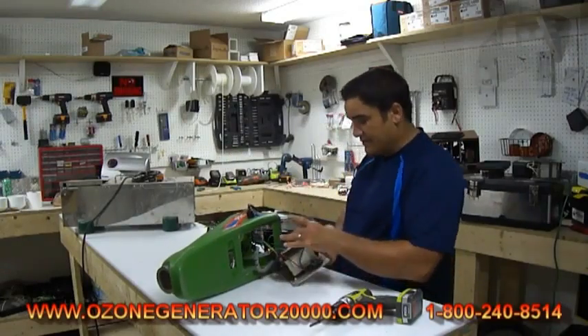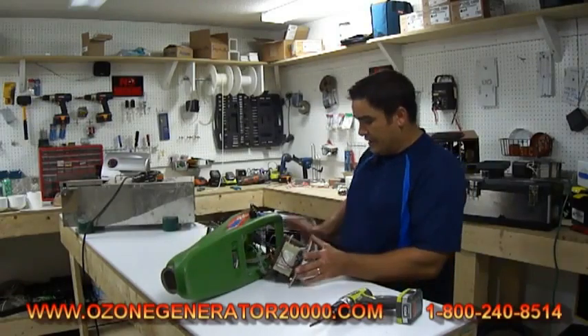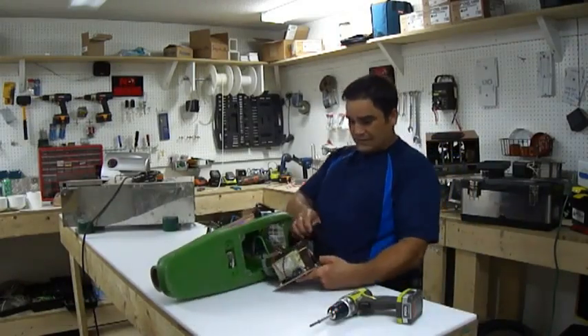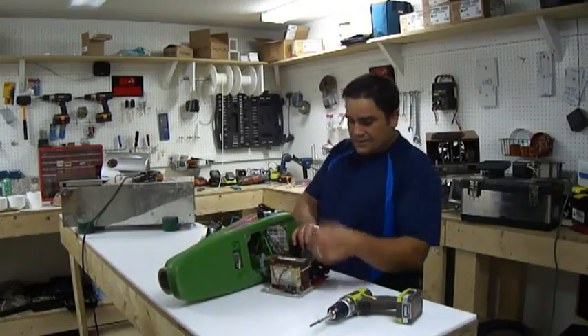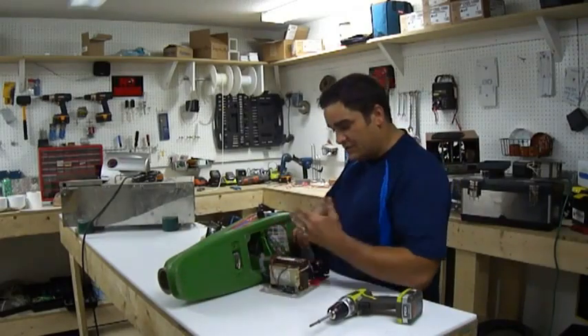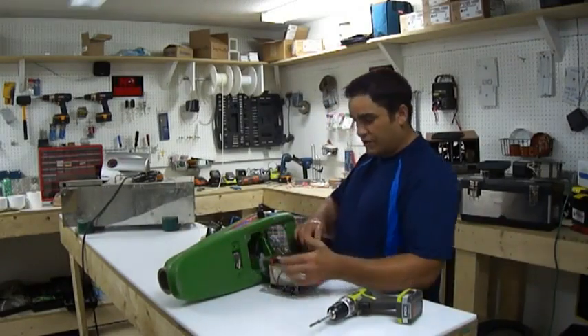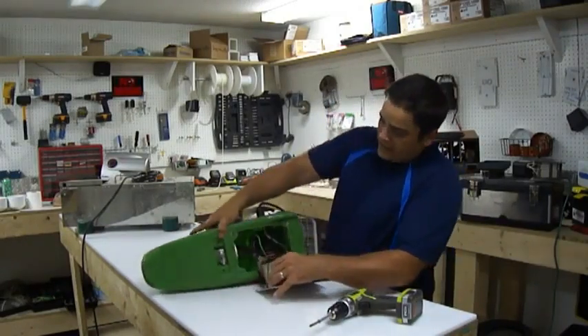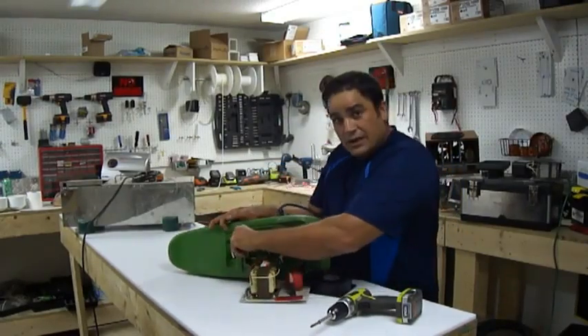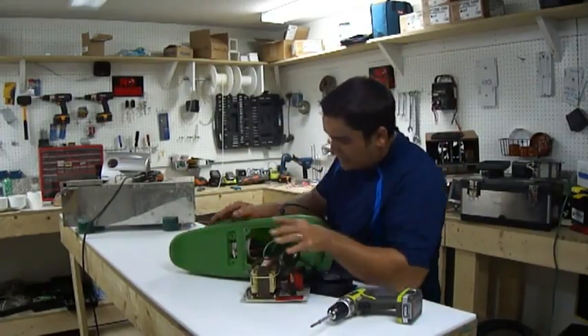And what you'll see is the transformer literally is almost the same height as this fan. So that means, again, this airflow is being robbed or hogged by the transformer before it can get to this tube. The tube is where our generator cells are.